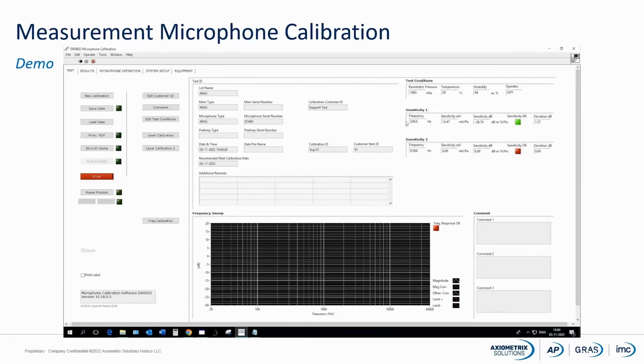That was the first part of the calibration, the piston phone part. Now we have switched off the piston phone and switched on the generator. We have done the voltage insert calibration, and we have calibrated the open circuit sensitivity for our microphone capsule. We can see that at 250 hertz we have the sensitivity in millivolt, 14.47. In dB relative to 1 volt per Pascal, it is minus 39.79, and we have a deviation from the nominal sensitivity. So this microphone is a little bit more sensitive than what we normally have for this type of microphone.